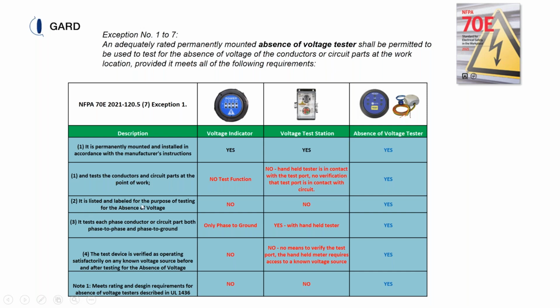2, it is listed and labeled for the purpose of testing for the absence of voltage. This voltage indicator is not listed and labeled as such. Neither is the voltage test station. The I Gard IAVT is. It tests each phase conductor or circuit phase to phase and phase to ground. This one only indicates phase to ground.